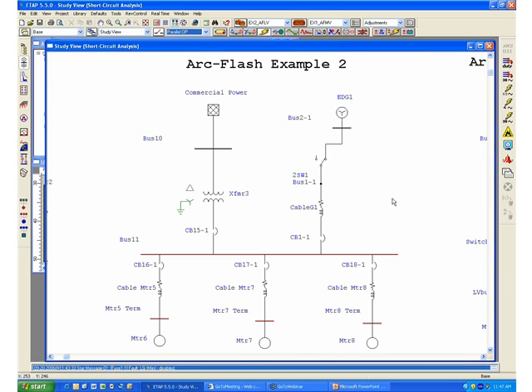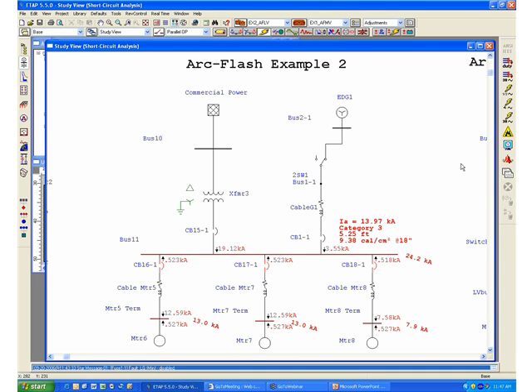For this particular case, we see that indeed, as we would expect, the highest amount of incident energy would be released in the event of an arc fault when you have both the operation of the emergency diesel generator in parallel with commercial utility power.